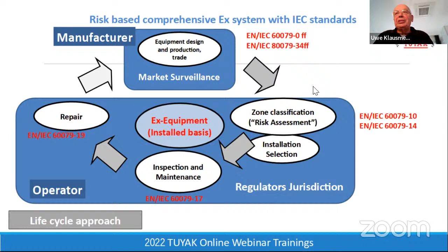So when you have installed everything, you can operate such a factory, but finally you have to make inspection and maintenance, and this is done according to part 17 from the standard group. Then finally you have to repair everything if there is a need to repair, and therefore we have the 60079-19 IEC standard, and there you can see guidance and the requirements for how to repair equipment and reinstall it, or to say, okay, we need a new one. So as you may see here, the whole life cycle is covered by IEC standards. And this is a very big advantage we have in explosion protection.